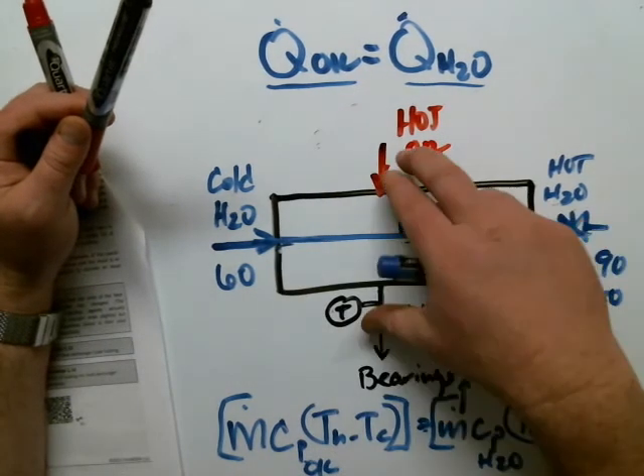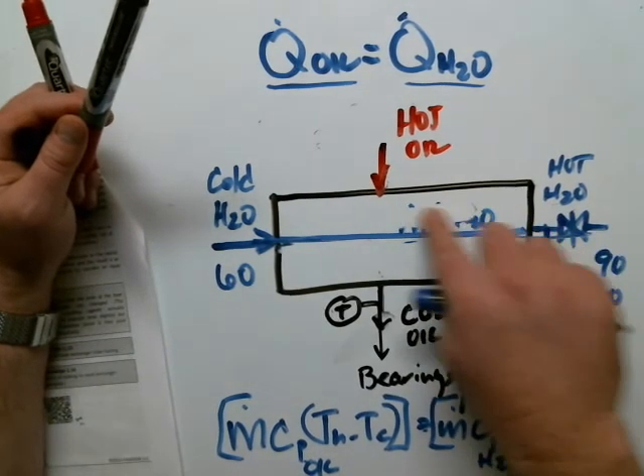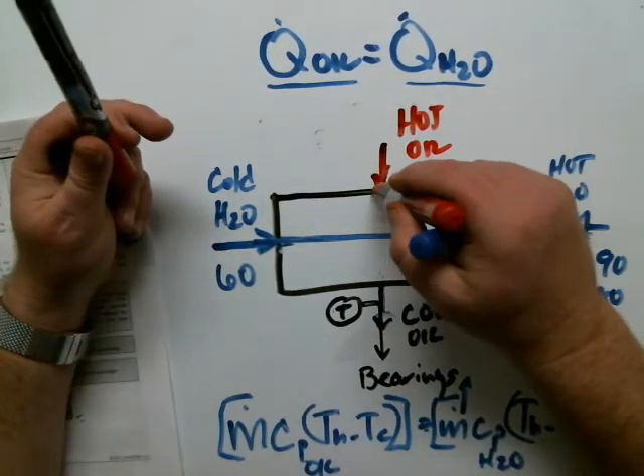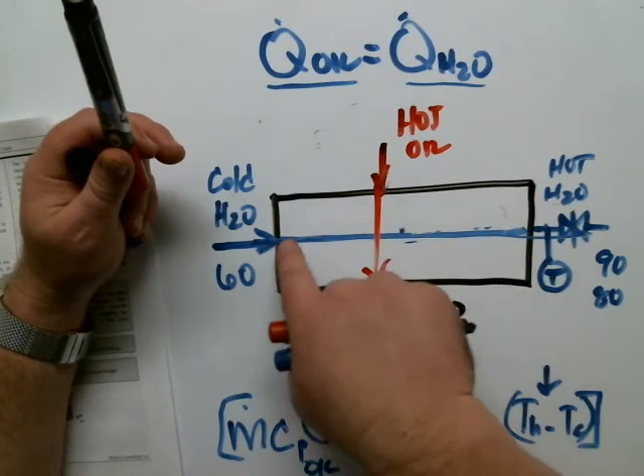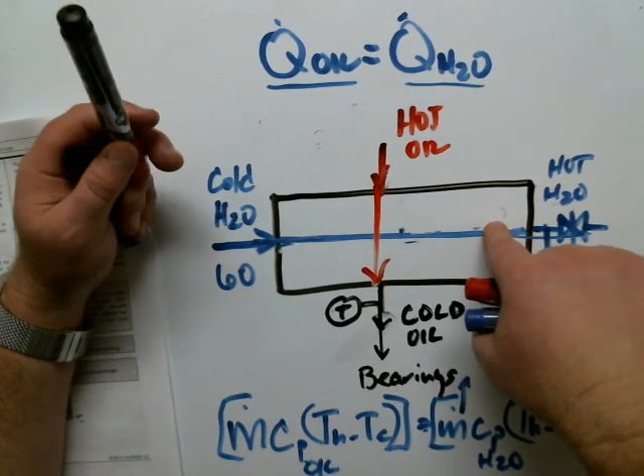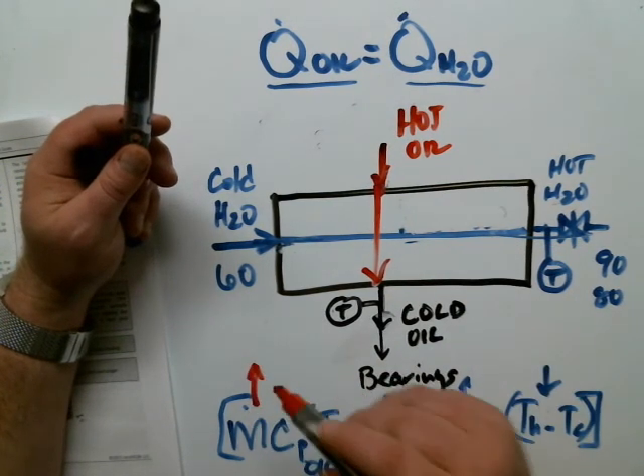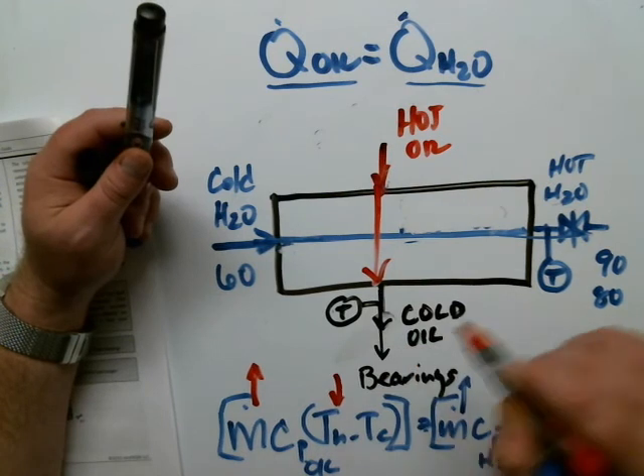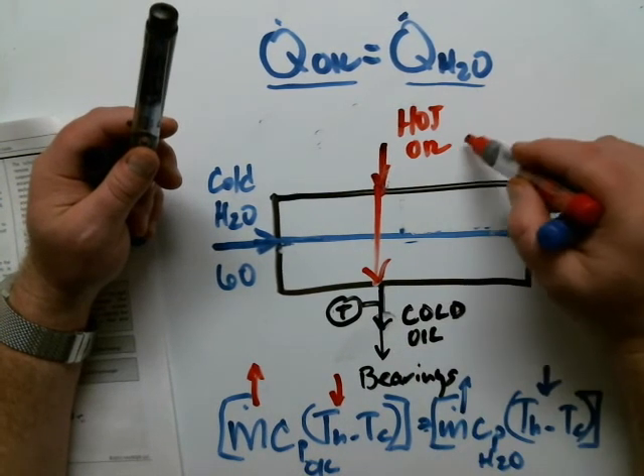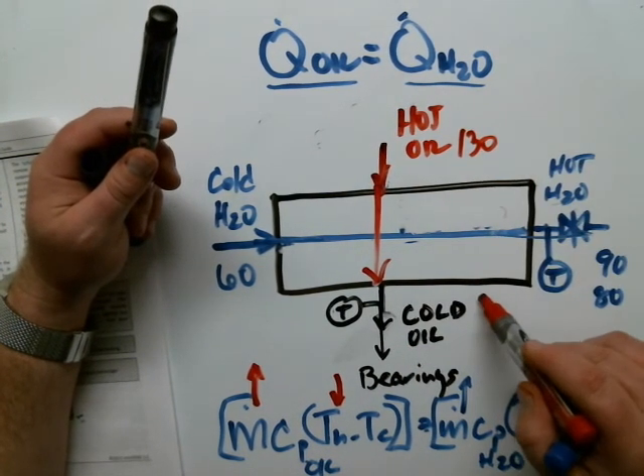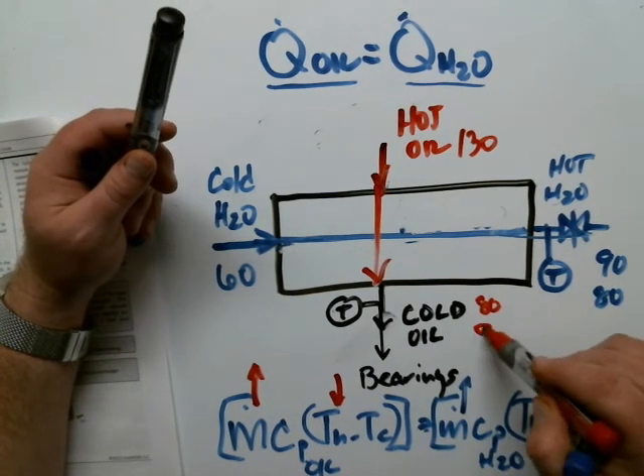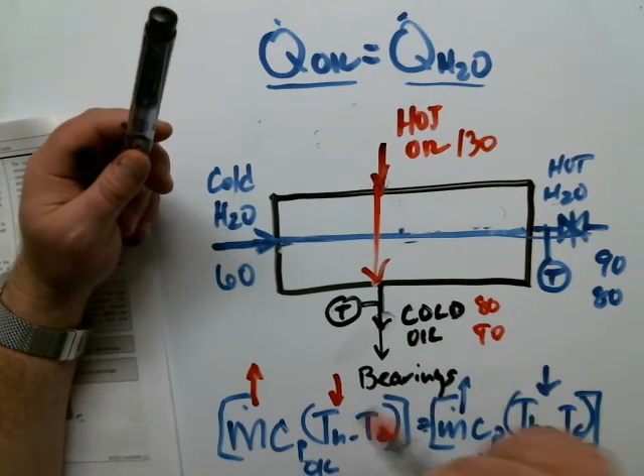Let's say I increased the flow rate of the oil. Kept the mass flow rate of the water constant. Well, if I increase the mass flow rate of the oil and keep the mass flow rate of the water the same, you can see that this is going to be going really fast, not being as in contact with the water as much, right? So the mass flow rate went up, but the differential temperature will actually go down. This would be sitting here at 130 degrees. And let's say it was 80 degrees leaving. Well, now it's going to possibly be leaving at 90 degrees. And you can see that delta T went down.